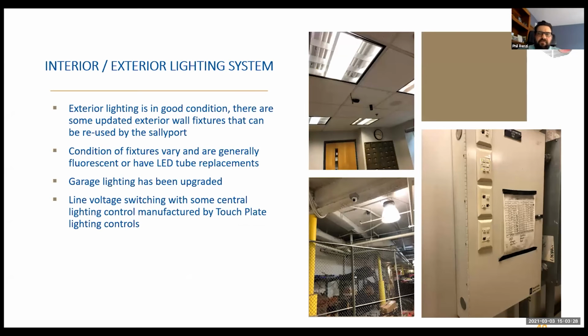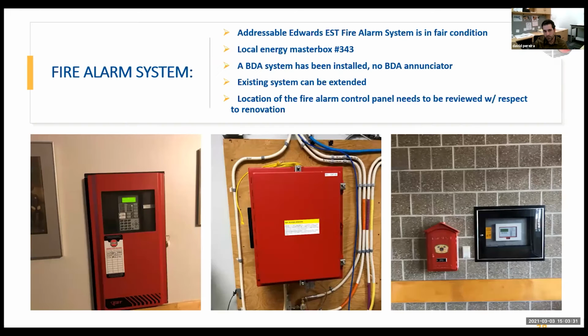Can I ask a quick question on the fire alarm panel? It's expandable, so it's taking into account all the new square footage and devices—that panel could handle if we added a dozen more, or even more than that. It's addressable, so we could add onto those loops and add power supplies for the notification appliances. There shouldn't be any issue reusing it.